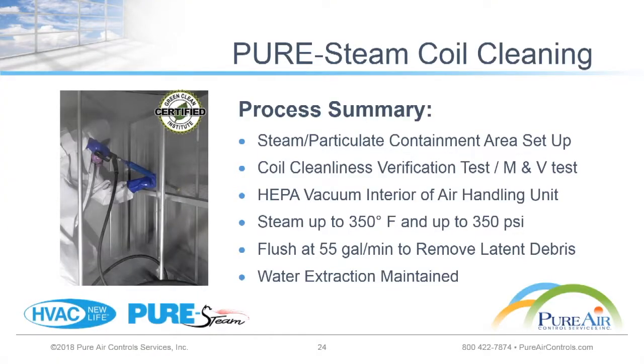So part of the development of this proprietary process is figuring out the ideal pressure to hit the coil with when we use our high temperature steam. We stick around 350 PSI because we found through a lot of trial and error that that's the perfect pressure to penetrate even thick coils, coils 16 inches thick, so that the steam and the combination of pressure can start breaking down the microbials and debris impacted inside that coil, so it can eventually start coming down and flowing out of the drain pan.